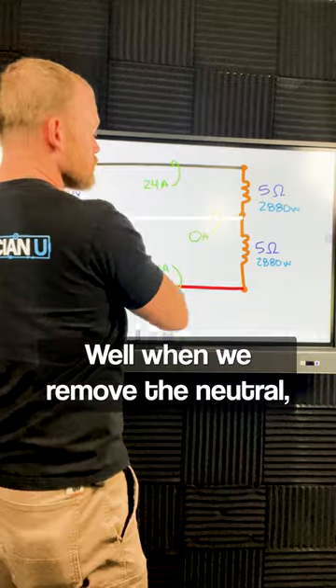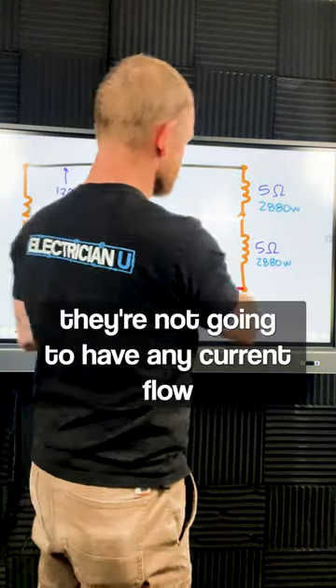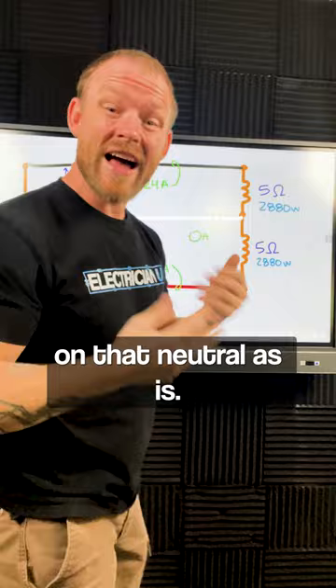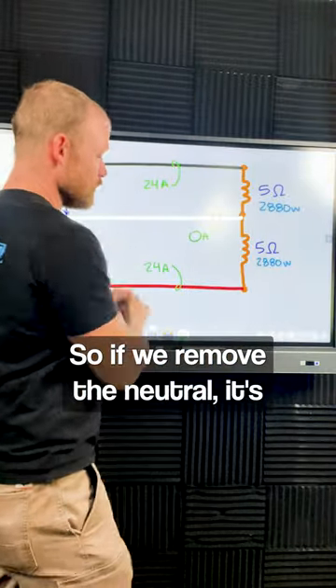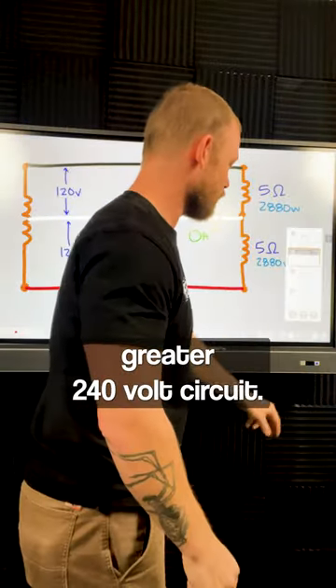Well, when we remove the neutral, it doesn't matter because we see already that because they're balanced, they're not going to have any current flow on that neutral as is. So if we remove the neutral, it's just going to become the greater 240-volt circuit.